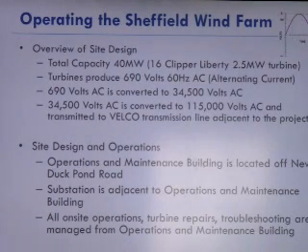in a transformer down there. That's stepped up to get it down to the substation, so you have a higher voltage for transmission of power. So that comes down to the substation. It goes through our large T1 transformer, which then steps it up again to 115,000 volts. That's transmission grade, which then leaves on the Velco line and into the grid.